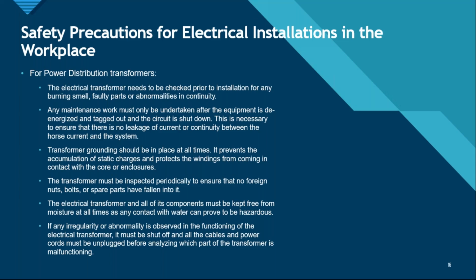When I was working back in the electrical field, there was this one case where we went to a site for testing and maintenance of electrical systems. What happened was we isolated the transformer. We checked the electrical drawing to check where the connection was coming from. We isolated the transformer to isolate all the electrical systems. Once the electrical systems are isolated, there is still stored energy, there is still stored electricity in the bus bars of the electrical panel. So all of that stored energy needs to be put into grounding, right, to truly isolate an electrical panel.